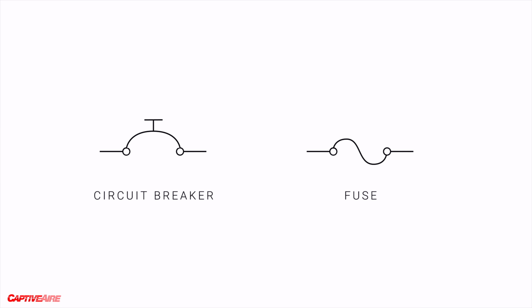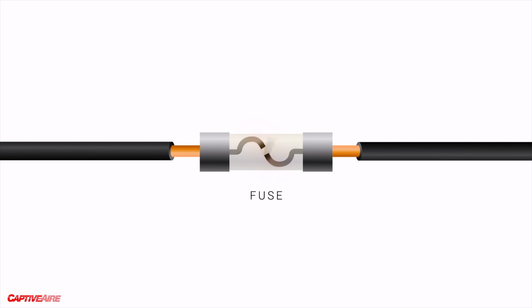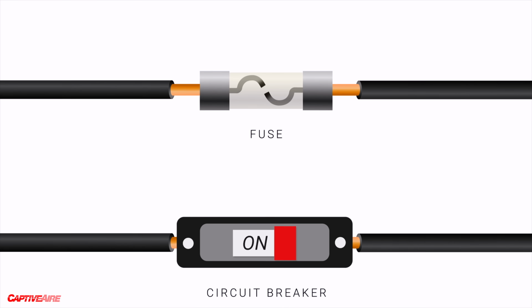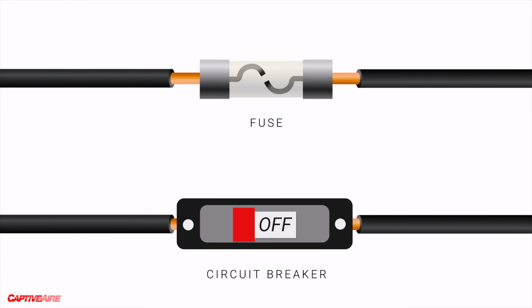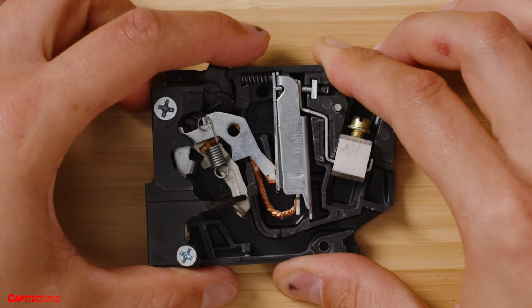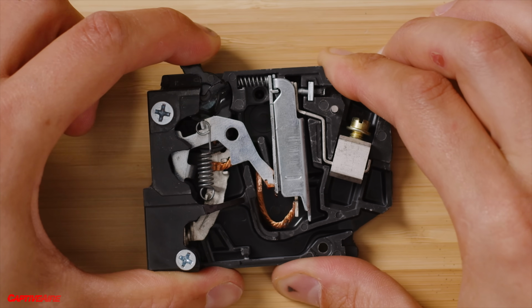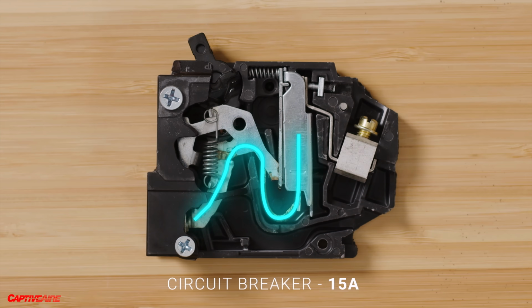The difference between a circuit breaker and a fuse is that a fuse just goes bad or opens when overloaded, while a circuit breaker trips but can be reset. I've actually taken apart this 15 amp circuit breaker so we can visualize this. When set to on, or closed, there's a path for the electricity to conduct through the circuit breaker.